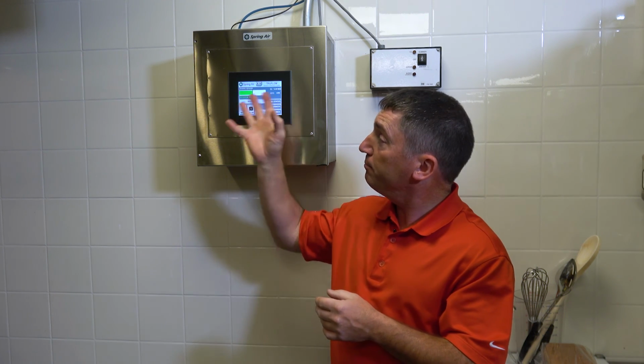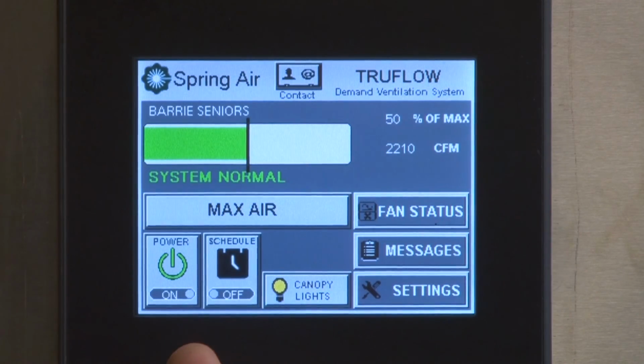From a keypad standpoint, it's basically just a general status. Cooking staff, you come in the morning, you can turn the system on as soon as you come in. The beauty of the TrueFlow is if the system's on but you're not cooking, it's going to run at a bare minimum ventilation rate. Then as you start cooking, it's going to ramp up automatically.